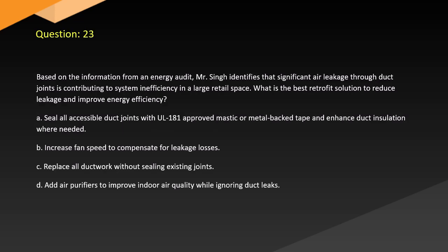Question 23. Based on the information from an energy audit, Singh identifies that significant air leakage through duct joints is contributing to system inefficiency in a large retail space. What is the best retrofit solution to reduce leakage and improve energy efficiency? A. Seal all accessible duct joints with UL 181 approved mastic or metal-backed tape and enhance duct insulation where needed.